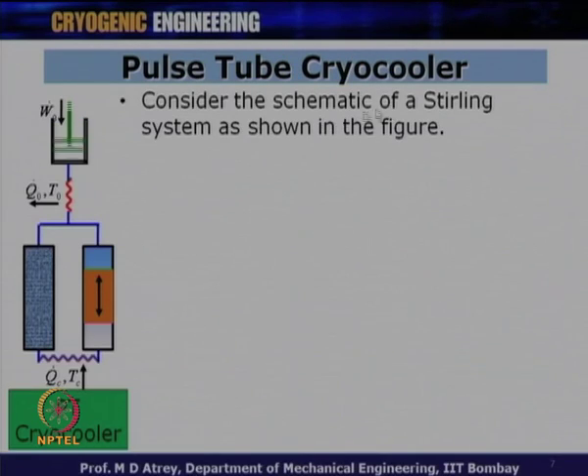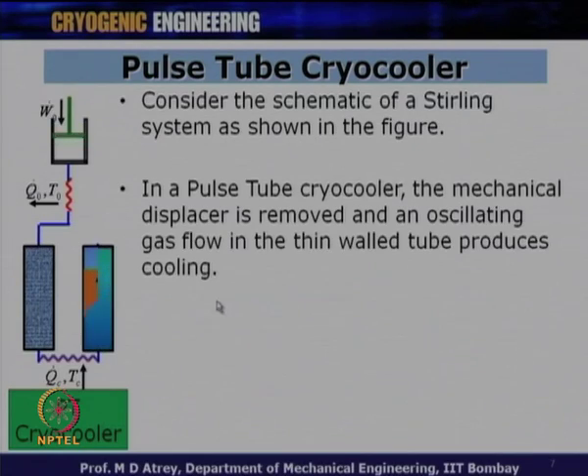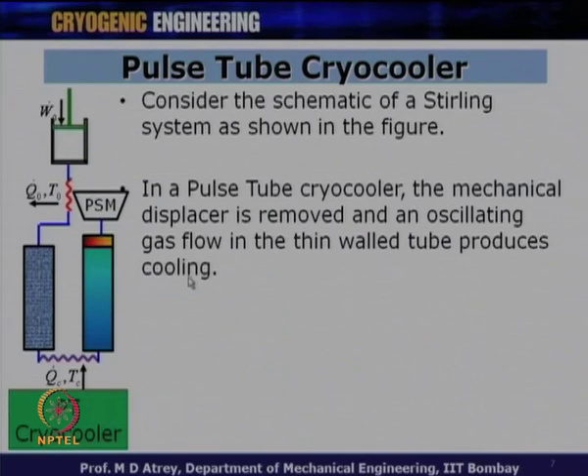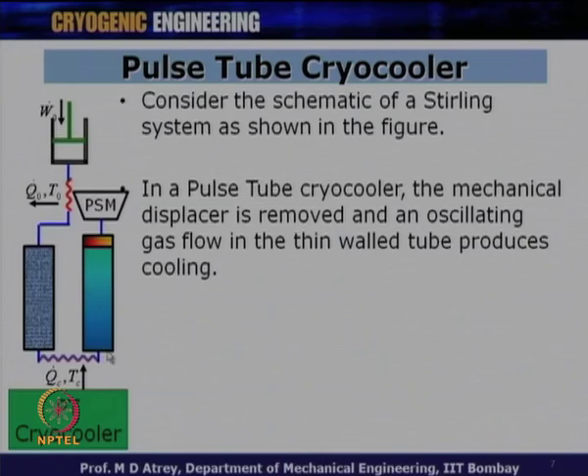Consider the schematic of a Stirling system. If I want to convert this to a pulse tube cryocooler, I will just replace the displacer with a gas column — a cylinder or tube filled with gas. In a pulse tube cryocooler, the mechanical displacer is removed and an oscillating gas flow in a thin-wall tube produces cooling. An empty tube filled with gas is subjected to oscillating pressurization and depressurization, and this generates cooling. This is a simple definition of a pulse tube cryocooler.